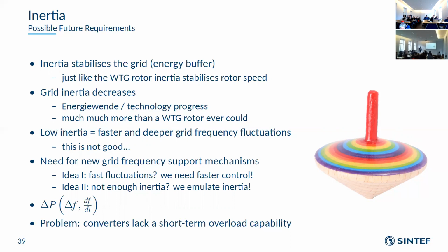But for any of these means, we still have the same problem mentioned several times: the converters lack short-term overload capability. Especially in these frequency moments, it could be that we just need a bit of extra power for one second, and it's very expensive to buy a bigger converter just for that. But there's actually no real way around it, because you cannot overload it just for a second, while all classical electric machinery, transformers, cables, everything like that, can be overloaded for a second with no problem. So also for this frequency support, we will see changes in the requirements and in the services for sure.